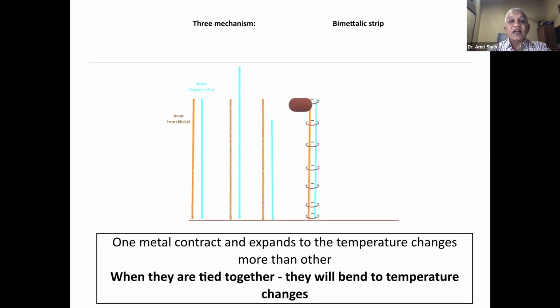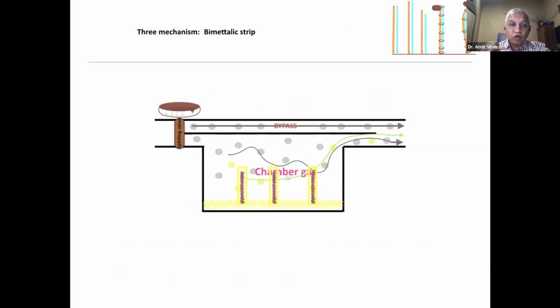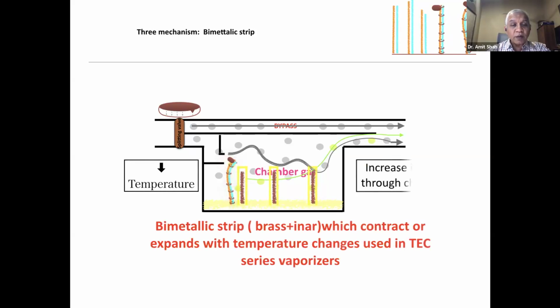Then what they have done is tie them together. So now when temperature changes, there is no way they can increase or decrease freely, so they'll bend because they are tied together. They've allowed a bending inside, which I'll again show you how it works. So iron and nickel, it is called INVAR. Here is a bimetallic strip, which is covering an opening. If there is a temperature drop, it bends because one contracts more than the other, which will open up this opening and allow more gas to pass. So this is part of most of our Tec vaporizers where there is a bimetallic strip. This is again just for the temperature compensation.